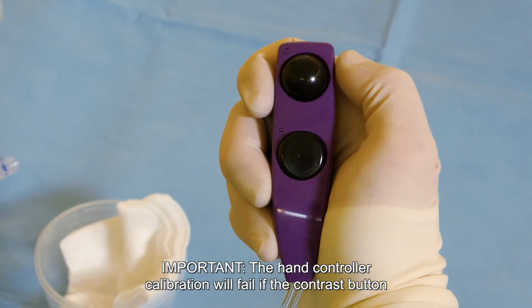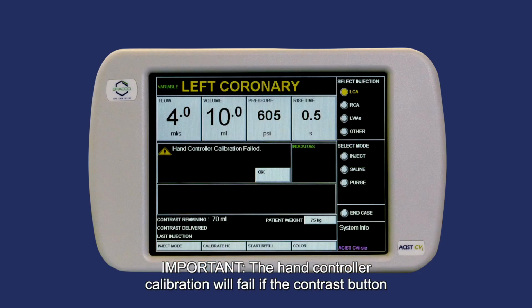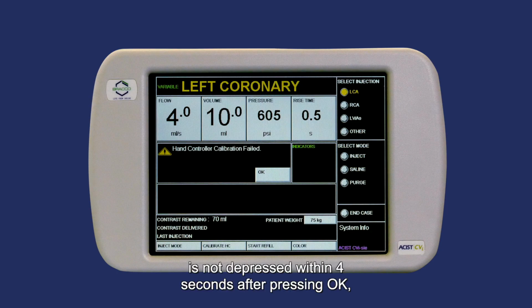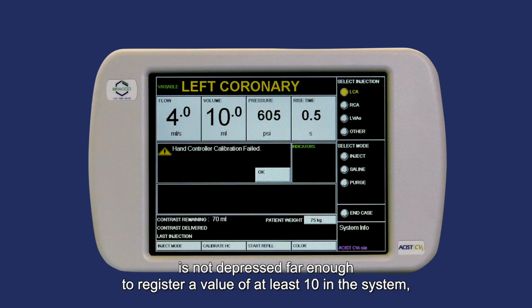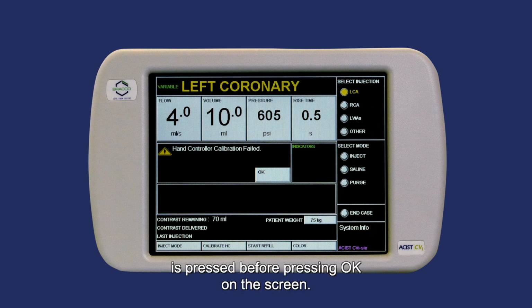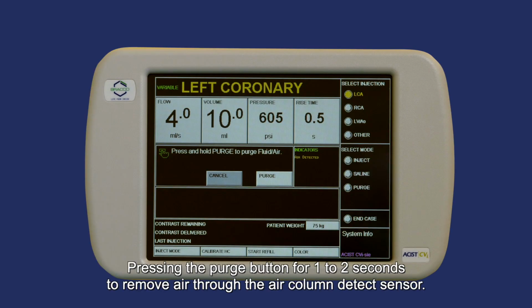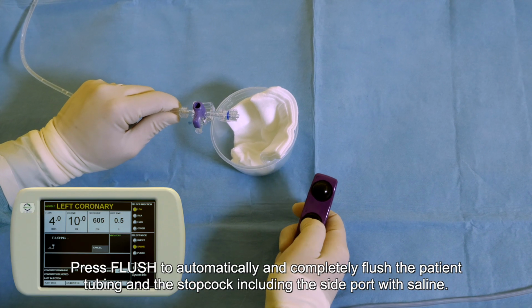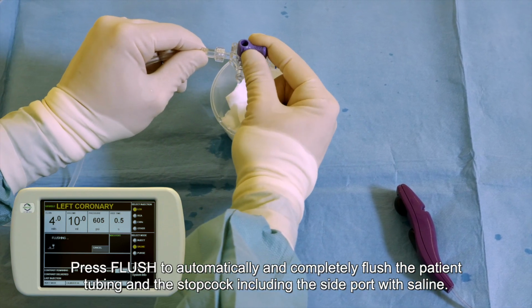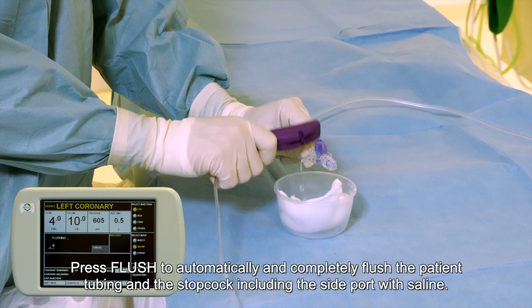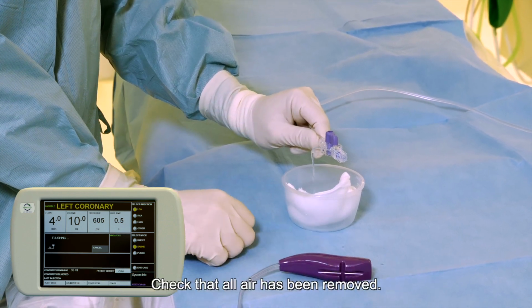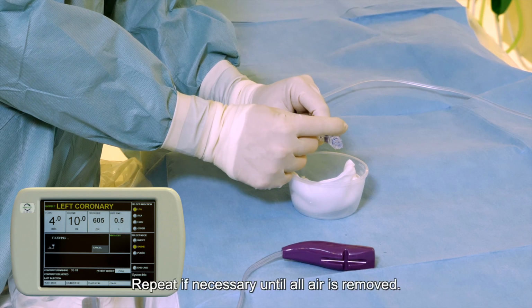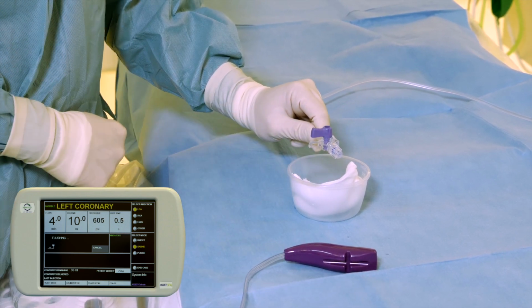Important: the hand controller calibration will fail if the contrast button is not depressed within 4 seconds after pressing OK, is not depressed far enough to register a value of at least 10 in the system, or is pressed before pressing OK on the screen. Press the purge button for 1 to 2 seconds to remove air through the air column detect sensor. Press Flush to automatically and completely flush the patient tubing and the stopcock, including the side ports, with saline. Check that all air has been removed. Repeat if necessary until all air is removed.